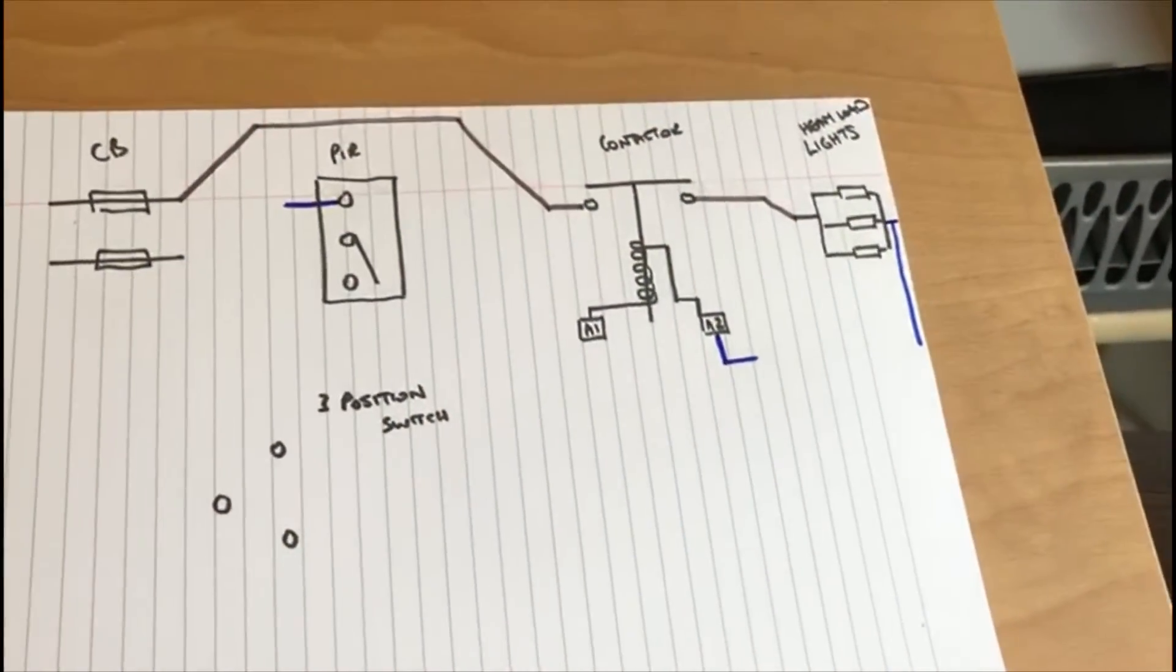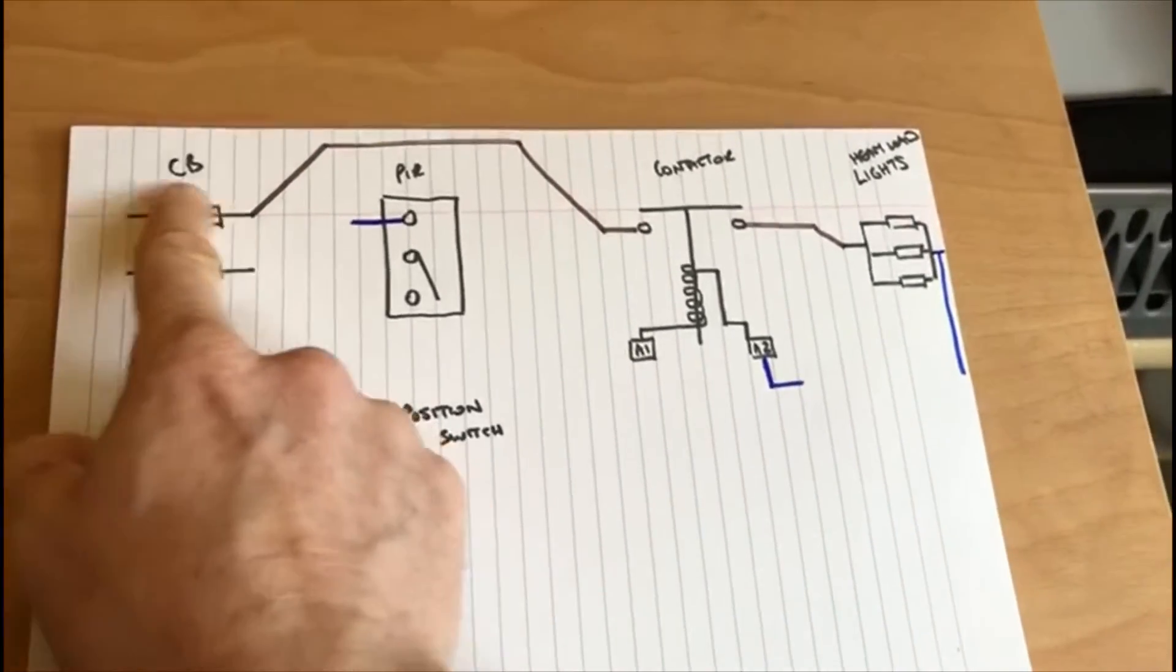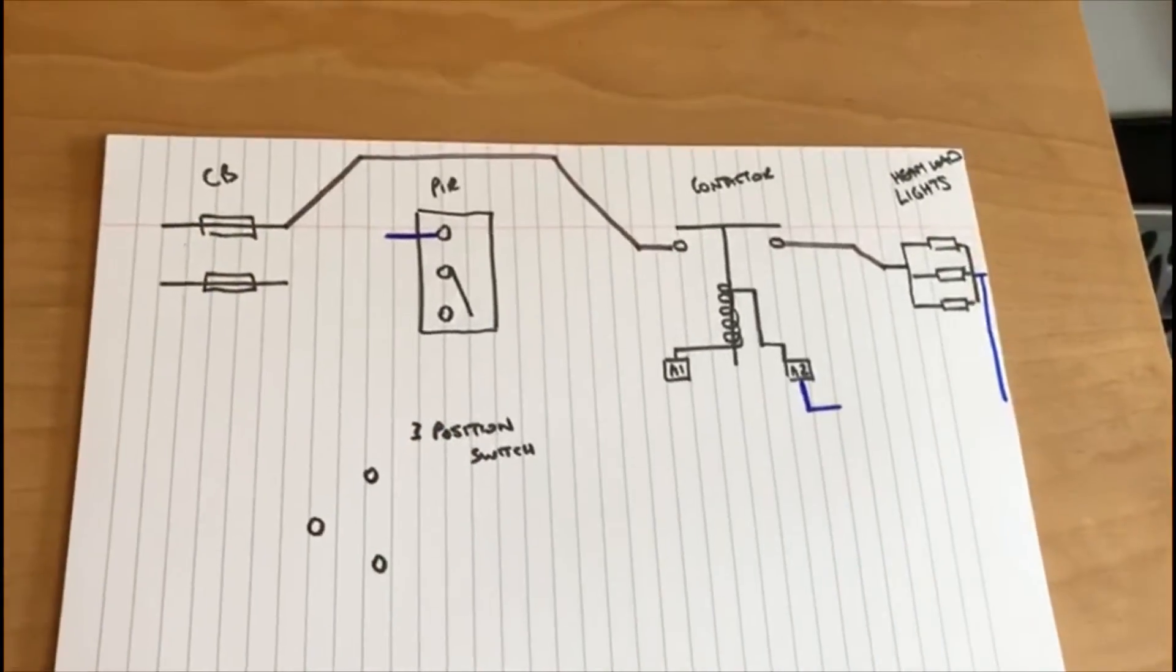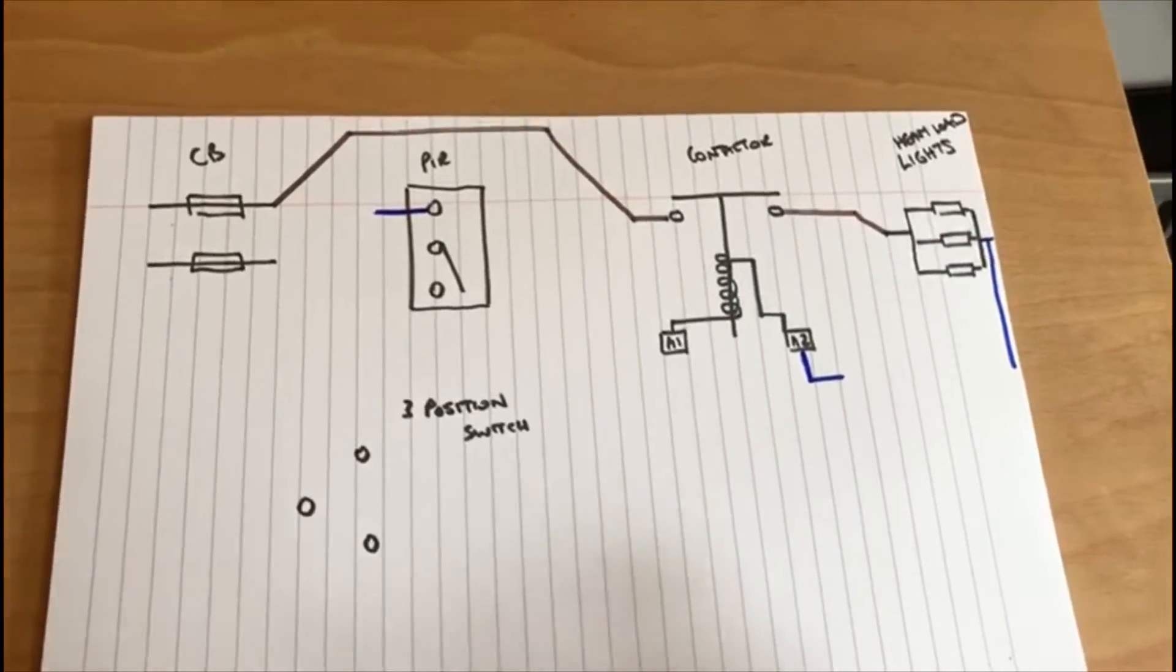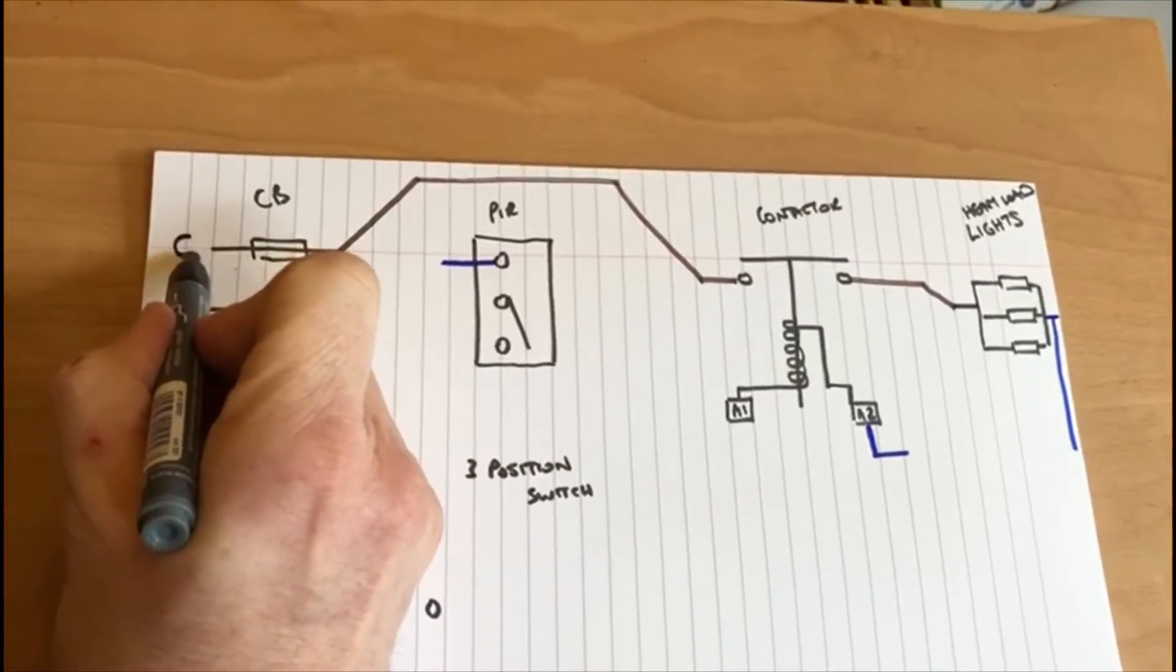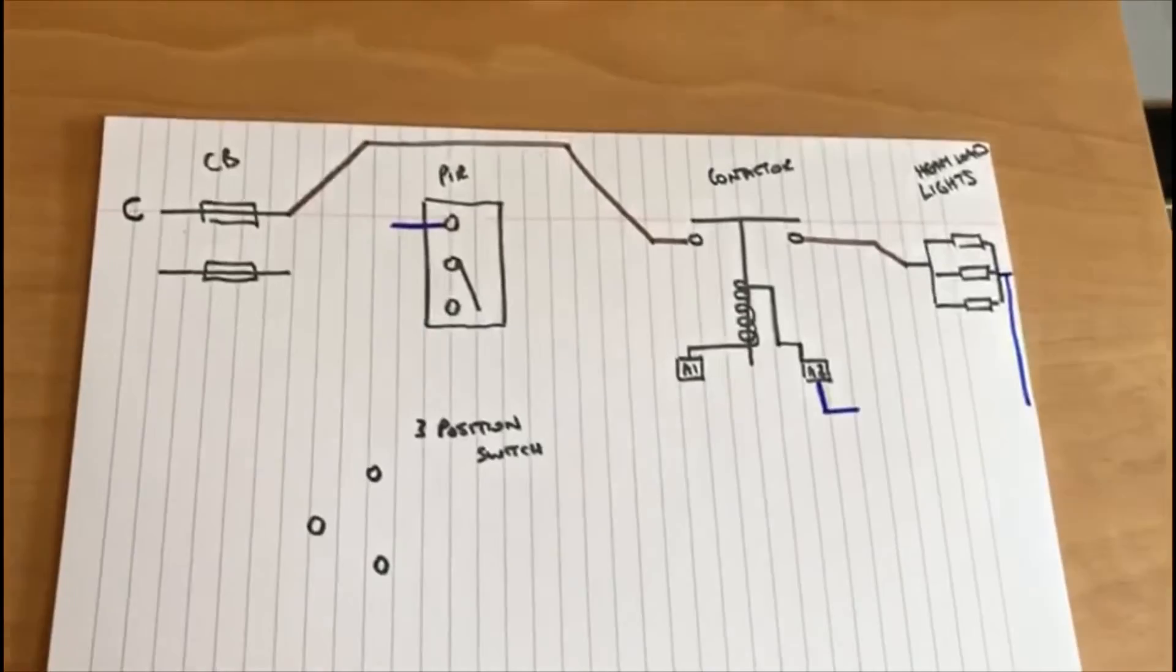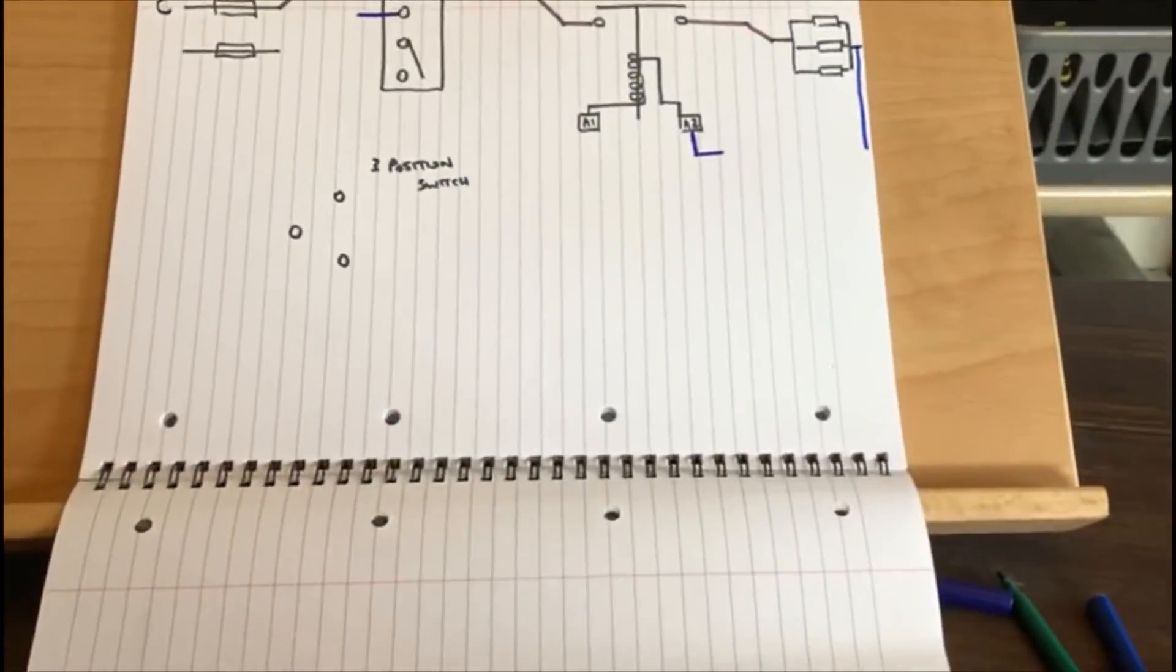In this case then it would need to be a slightly bigger circuit breaker and the right size contactor as well. So this one could be, we might need it to be a C type circuit breaker. Now the rest of the circuit diagram is now very similar to the one previously.